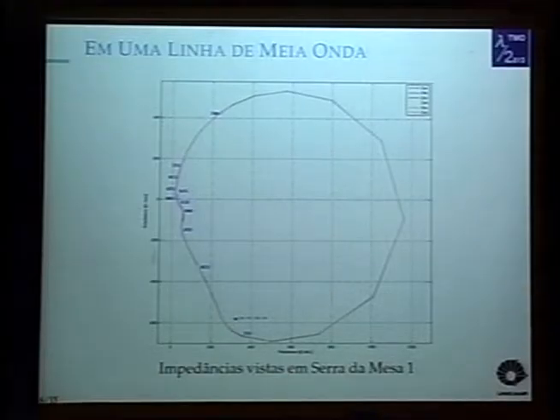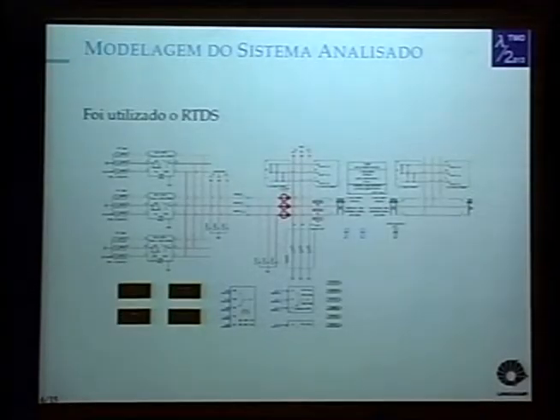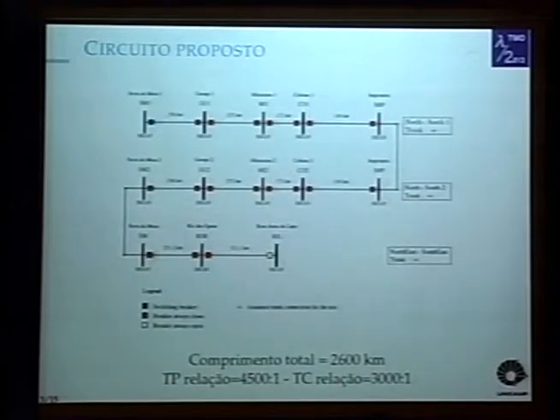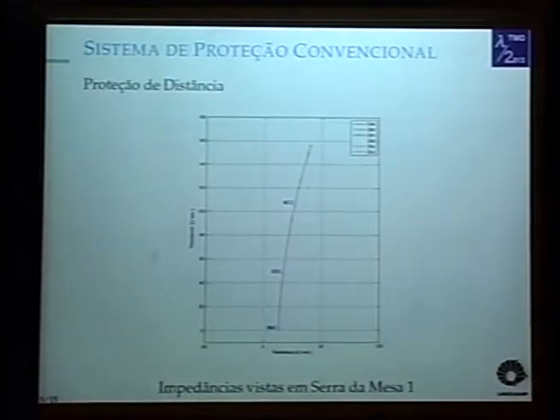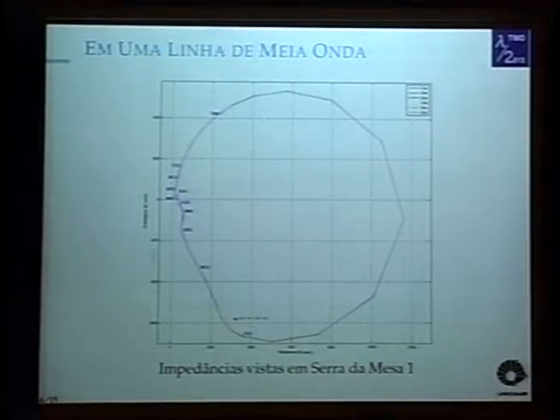We know that between Serra da Mesa 1 and Gurupi 1 there is a physical distance of 250 kilometers. Between Imperatriz and Colinas 2, 330 kilometers. They are almost identical. There's 80 kilometers of difference. However, the impedance between Imperatriz and Colinas 2 changes a lot more.